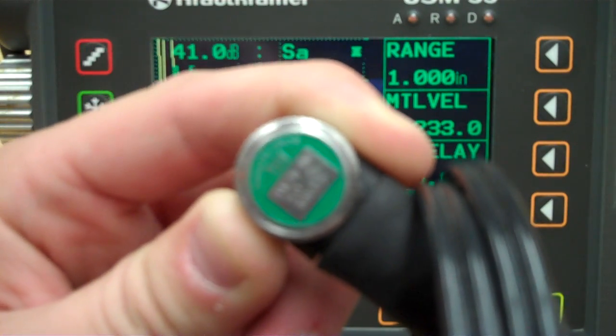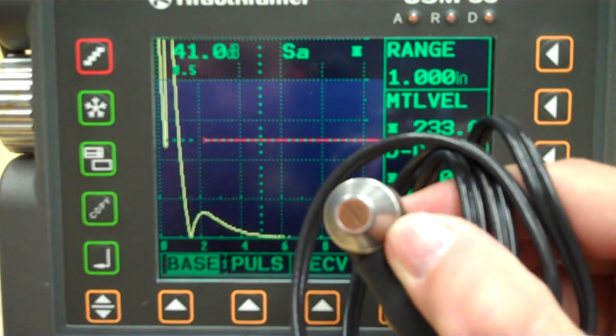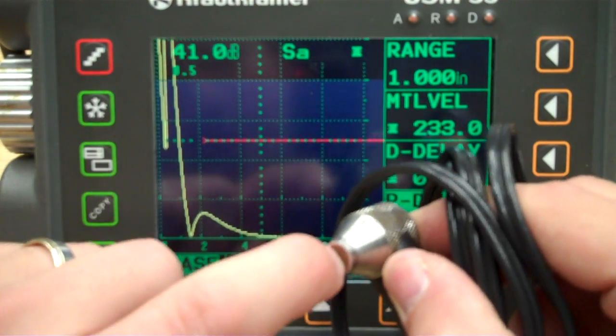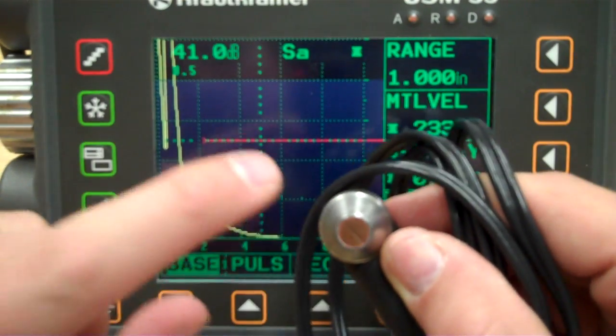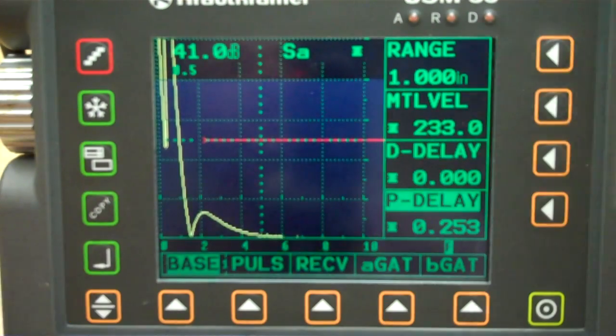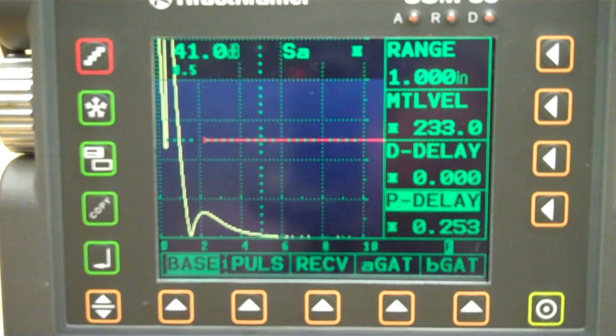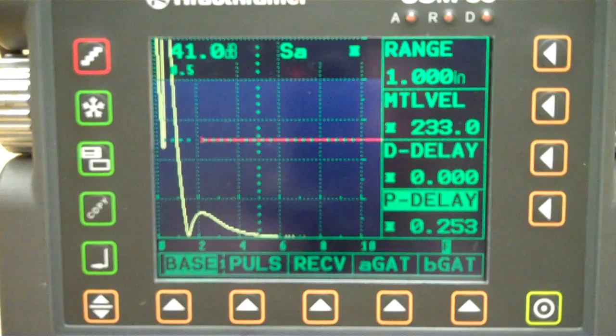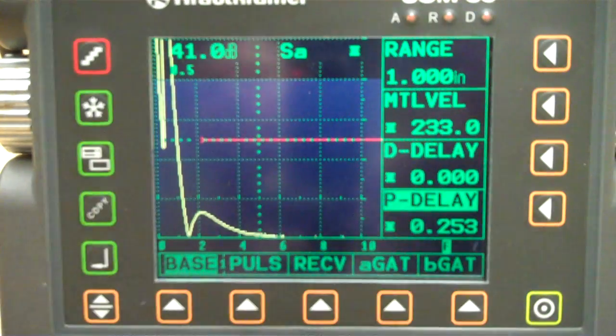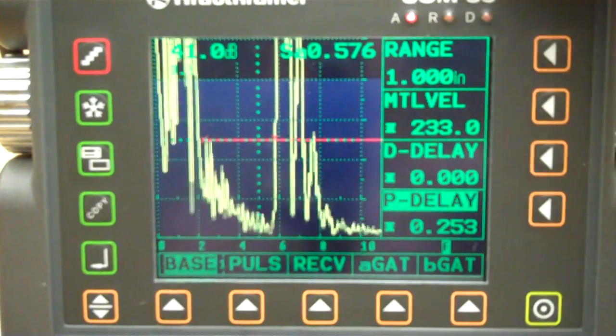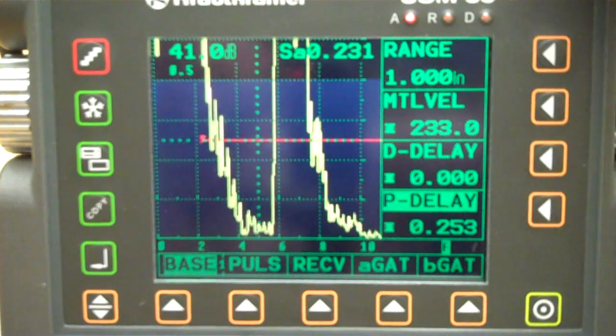Let's get it up here close enough so we can be right in your face. Like I said, 5 megahertz, quarter-inch diameter. Here we've got the two elements. We've got one element over here, another element over here with a crosstalk barrier in between. And that's going to keep those guys from talking back and forth to one another. So what we want to do is look at the difference between plain old compressional beam and then dual element. Last video was plain old compressional beam, single element stuff. Now we're going to switch over to dual element compression.